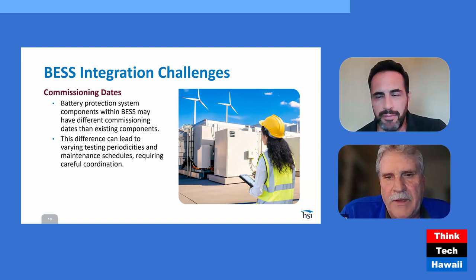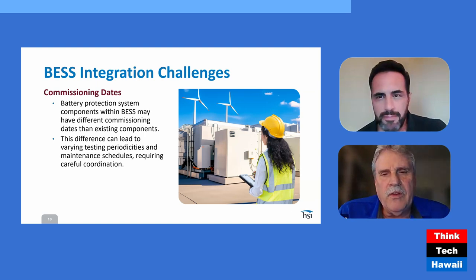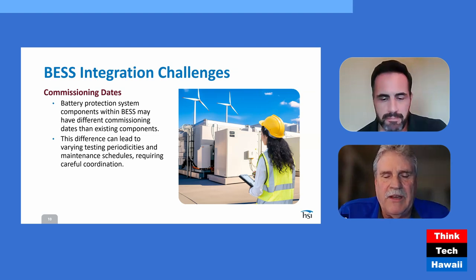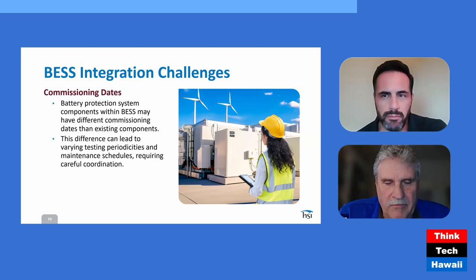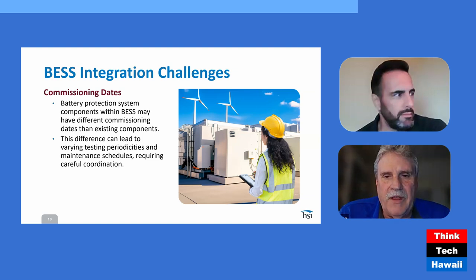We touched on that a little. Once again, if you're adding a facility like this to an existing site, you already have a plan in place. You have a protection system maintenance and testing document. If you're in compliance with the PRC-005 standard, you have that document and you're using it. So that's going to need to be revised. The list of equipment included in your protection plan is going to change because you'll have new protective devices there.